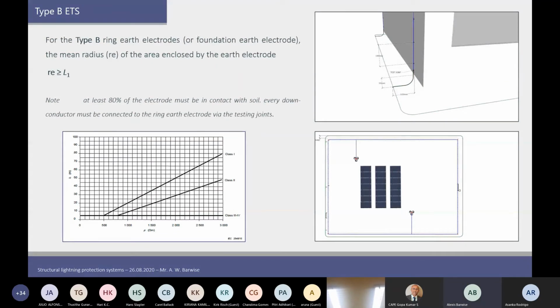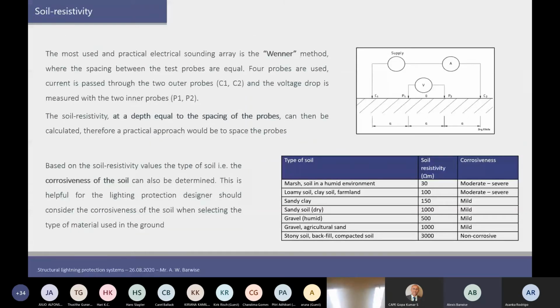So soil resistivity is a value not so commonly obtained because we don't have the instruments or we don't have the skill level in country. So there is also in the table quite an interesting way to go about this, to say if you don't know or cannot measure the soil resistivity, look at this. If you are in a marshland, very wet, very humid environment, you're going to expect very low soil resistivity values, 30 to 100 ohm meters. If you are in very clay conditions, you're at 150 ohm meters as an average value. Moving on towards maybe gravel, normal agricultural soils and sand where we have our maize planted, we're looking at about 1,000 ohm meters. And if we are in rocky, stony type soil, we have very high ohm meters. And so this is at least an indication.